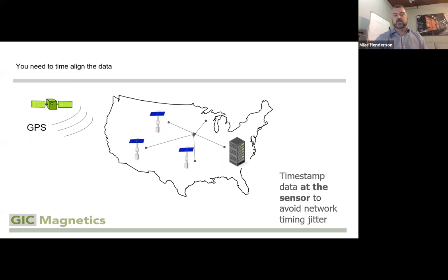The easiest or most tempting way is to record the time at the collection point, the server, but then you run into network timing jitter—communication paths differ, someone may be streaming Netflix at the office where the server is, and suddenly there's delay. What's supposed to be 12 noon for one sensor isn't 12 noon for the other. The best way to handle this is to synchronize the sensors with GPS, timestamping the data with a UTC reference right at the source, so you don't worry about propagation delay through the network.